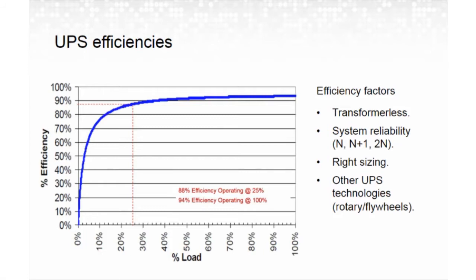Under normal conditions, neither one of those is operating over 50%, so you're more in that 30% range, so you can have a very inefficient system based on the redundancy and reliability of that system. Some other things you can look at are different UPS technologies. Some rotary systems out there have a higher efficiency. And then the other thing is just right-sizing the equipment.